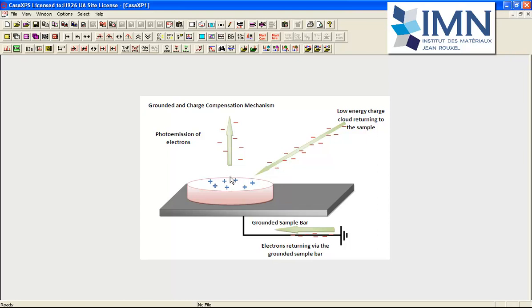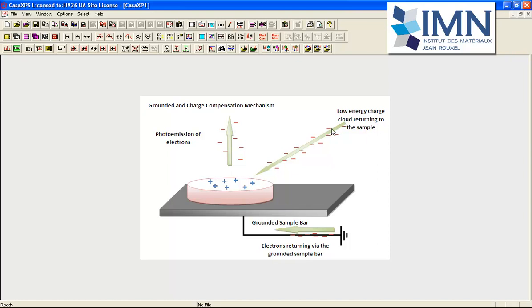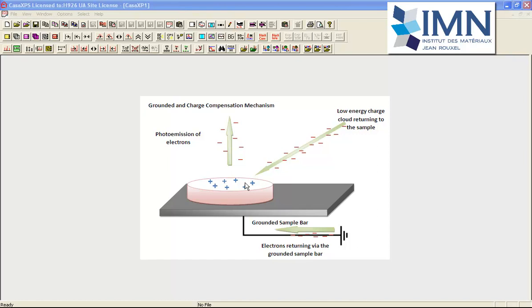Our ability to identify binding energy and well-formed peaks is contingent on having a suitable charge compensation mechanism that might be a combination of low energy electrons returning to the surface using a filament or an electron gun and then potentially also an ion gun. These are all mechanisms designed to maintain a stable charge state at the surface to allow the measurement of XPS spectra where the binding energy can be relied upon.